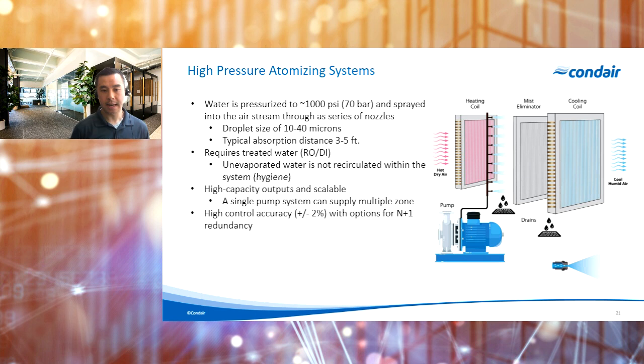So the next technology that we'll talk about here is what we call high pressure atomizing systems. So in this case, the system works by spraying high pressure water, typically at about 1,000 PSI, directly into the airstream where it's evaporated. Because we're spraying at fairly high pressure, droplet sizes here range in the 10 to 40 micron range. So we do still get very, very good evaporation because of the size of those droplets.